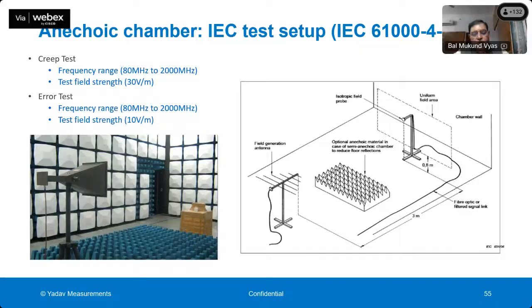Another important thing is, when this test is being conducted, it should not get influenced by the outside radio frequency. So this chamber is totally shielded against the radio frequency. When the meter is kept inside this chamber on a turntable, which can rotate 360 degrees, any radio frequency from outside cannot get into this chamber, and similarly no radio frequency from inside the chamber can get out of this chamber. So this is fully shielded.